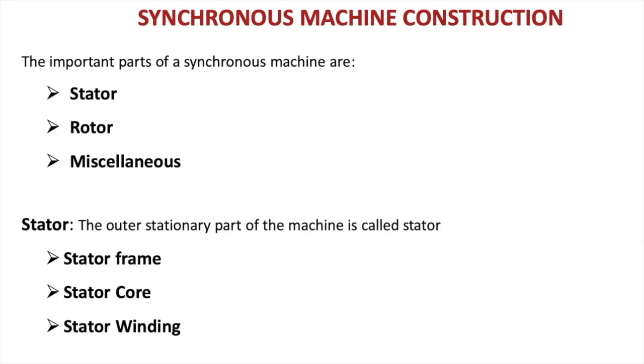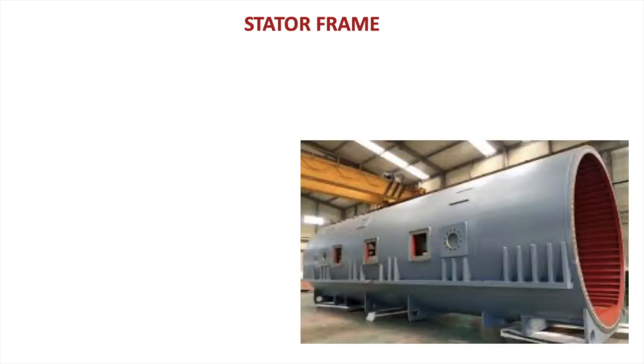Then we'll come to the stator. The outer stationary part of the machine is called the stator. It contains the stator frame, stator core and winding. So you can look at the stator frame. These alternators are normally of a very high rating. That's the reason I have taken a pic of such a large stator frame.